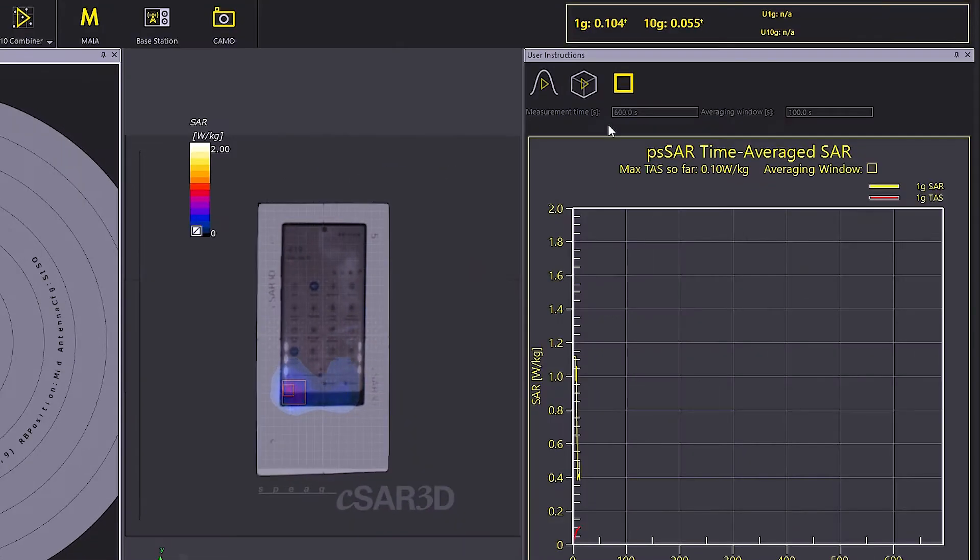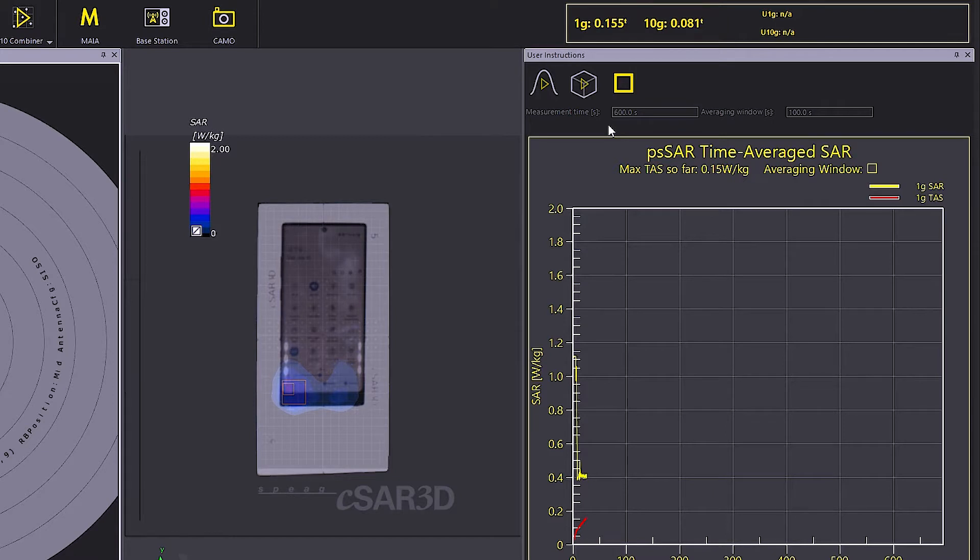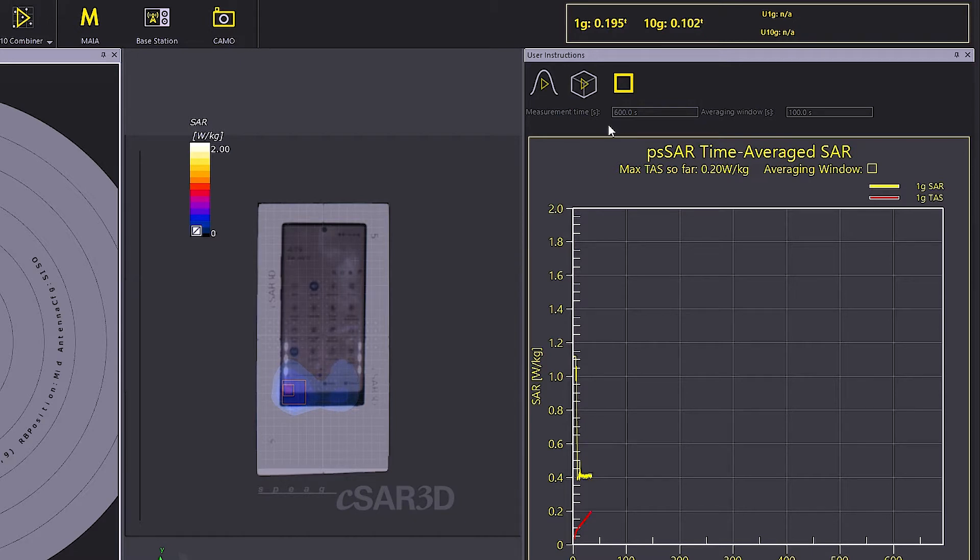I get nearly 3 updates per second. This includes acquisition, reconstruction, averaging and visualization of the results. This means that any fast variations in device SAR will also be precisely captured and included in the TAS calculations.